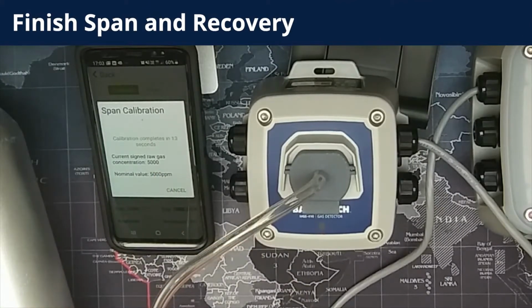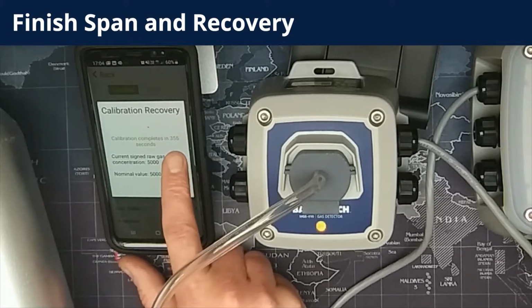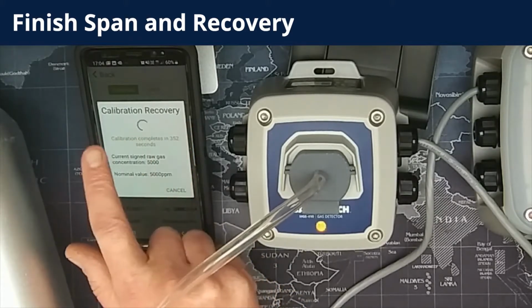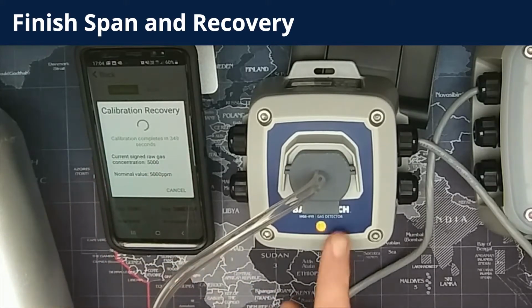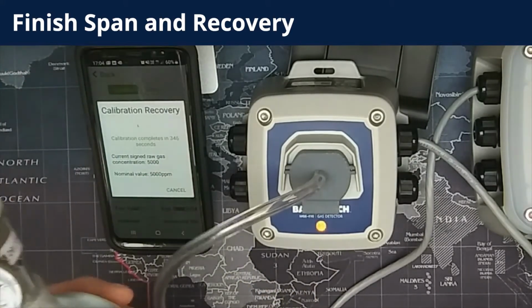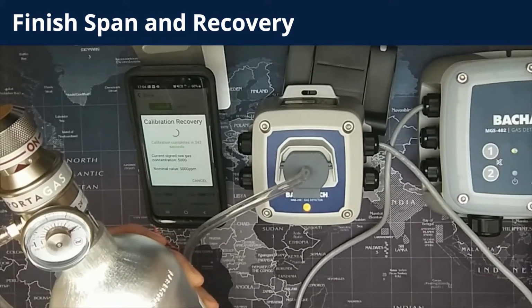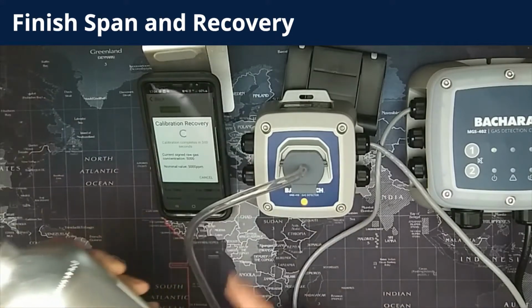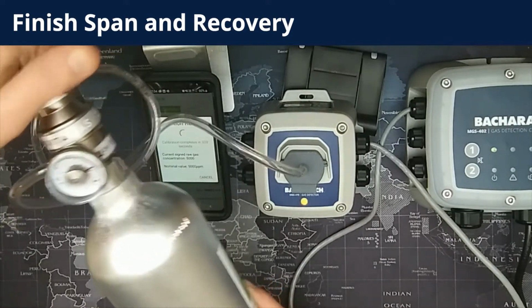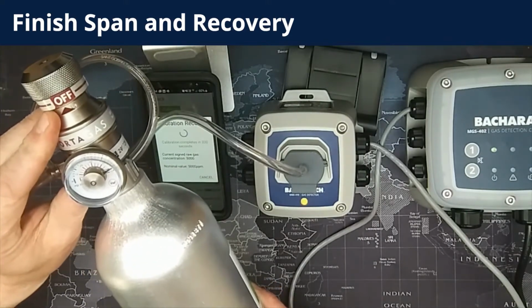So now we move on to finishing the span. You can see that the countdown has almost reached 0, and you can also note the LED light sequence. As soon as it reaches 0, the countdown flicks over into calibration recovery, and it starts another countdown. This is the recovery process for the sensor in the gas detector. Again, the LED sequence changes. The details of those colors are noted in the manual. You can now turn the regulator off because the span process is finished. We're in calibration recovery. So you can stop flowing the span gas to the detector. You can then take the calibration adapter off the detector, and you simply wait for the calibration recovery countdown to get to 0 seconds.